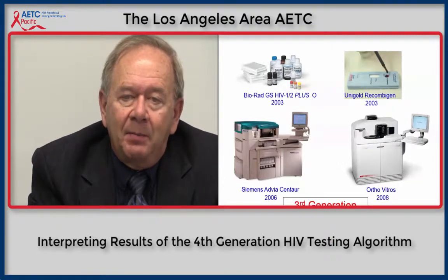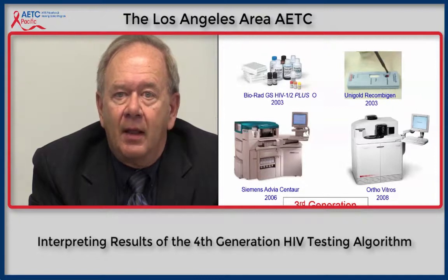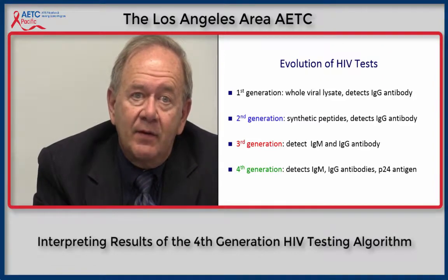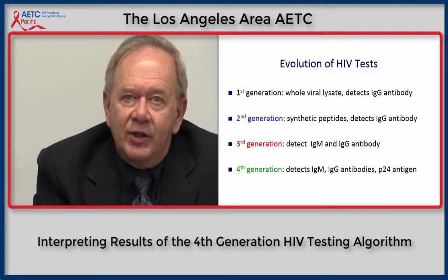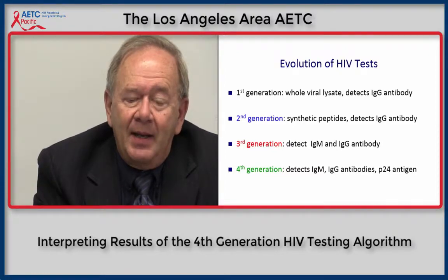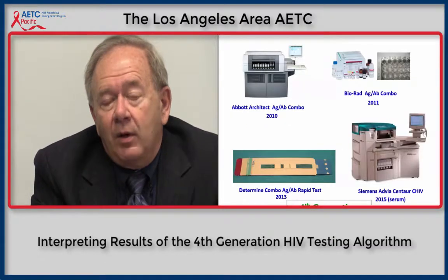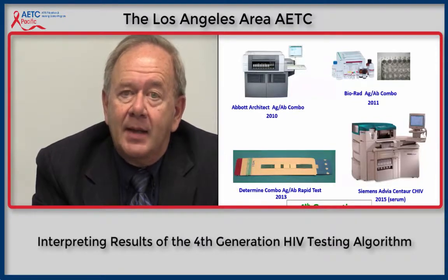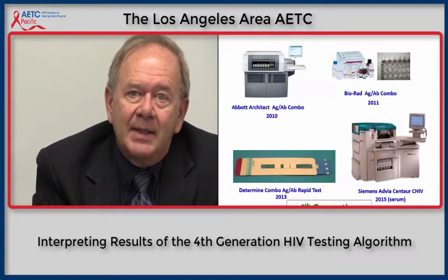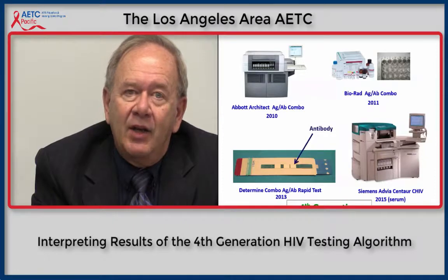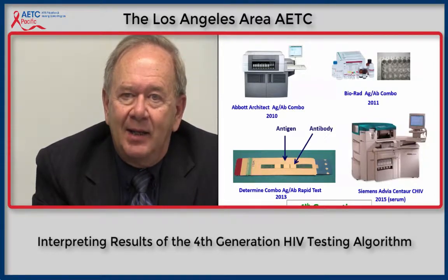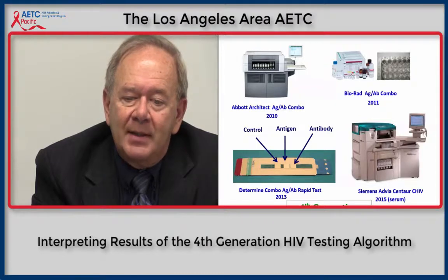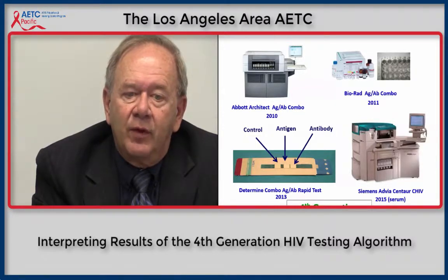Two other multi-platform analyzers — the Siemens Advia Centaur and the Ortho Vitros — can be used for third-generation testing. The fourth-generation is the most recent development, first approved by the FDA in 2010. It detects IgM antibodies, IgG antibodies, and also P-24 antigen. The four currently FDA-approved fourth-generation tests include the Abbott Architect, the Bio-Rad Antigen Antibody Combo Assay, the Determine Rapid Test, and the most recently approved Siemens Advia Centaur chemiluminescent assay in 2015, approved for use with serum specimens. The Determine Rapid Test can detect separately HIV antibody in one location, P-24 antigen in the second location, as well as the internal control.